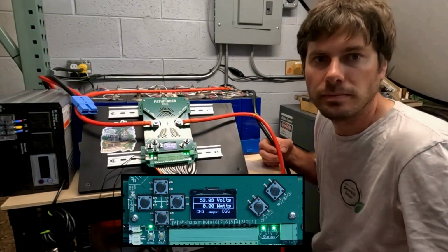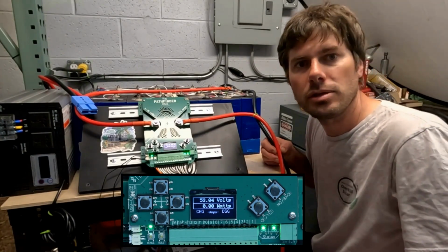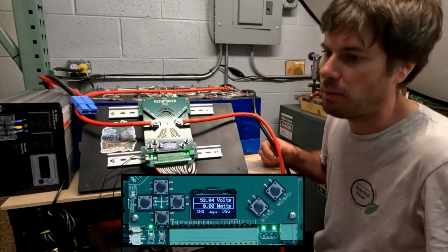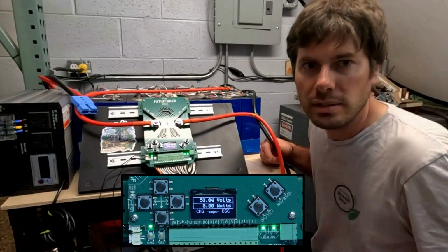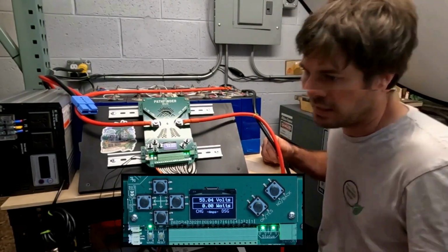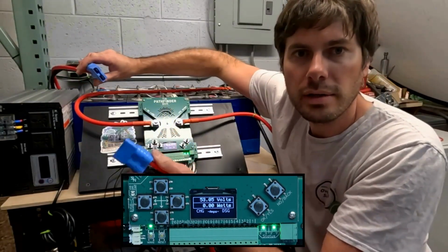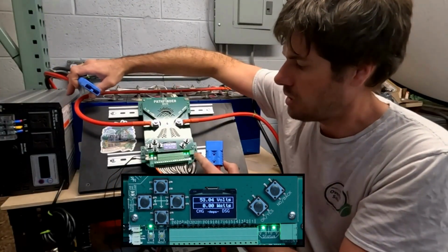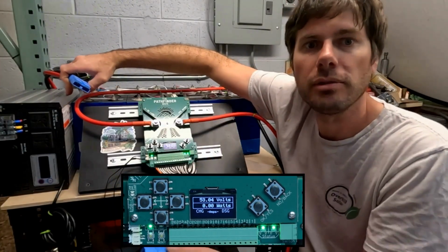When you don't have that, you would have to manually connect a resistor across the BMS in order to power on the inverter without triggering the short circuit. When I plug in my inverter to this battery, the BMS is going to shut off because it'll detect a short circuit from the capacitor inrush.